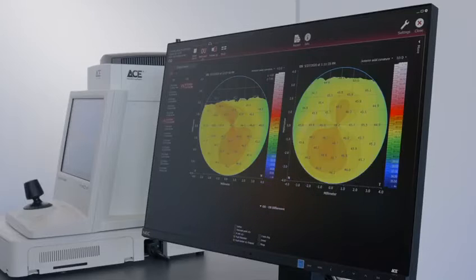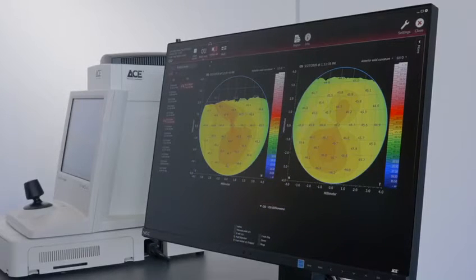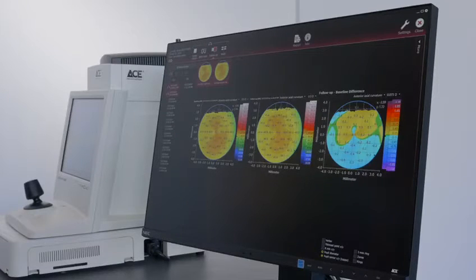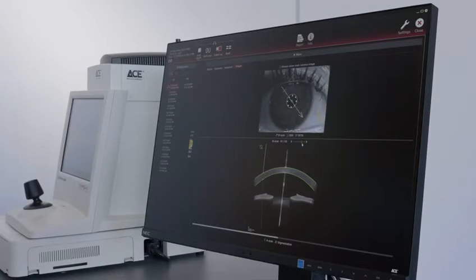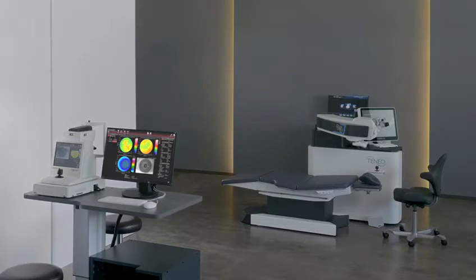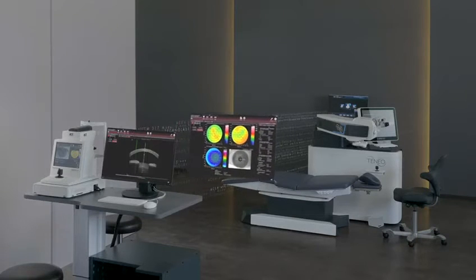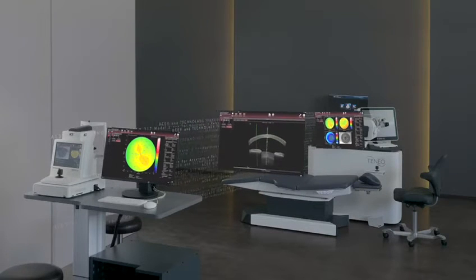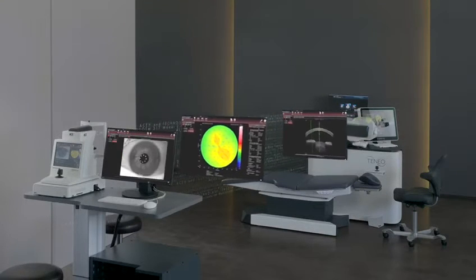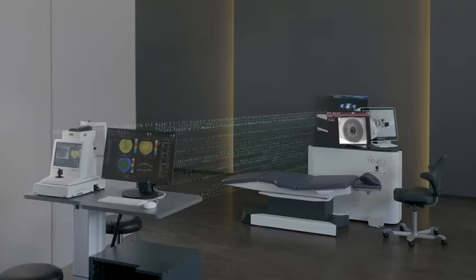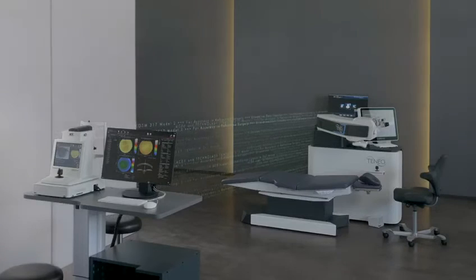Streamlined data transfer between ACE and the Technolas Teneo 317 Model 2 provides data supporting ProScan treatments with cyclotorsion compensation based on iris data. The ACE exports OTE files to the database server unit, including K, Q, pachymetry, topography, and iris images.